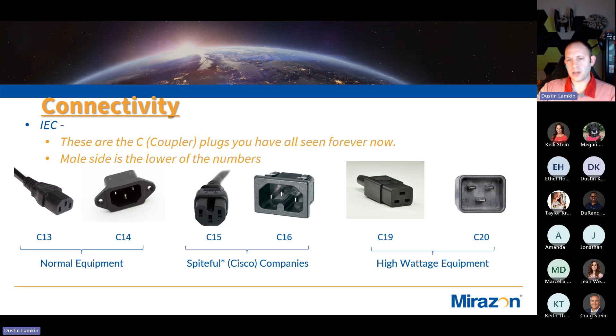So, PDUs—why do we need them? PDUs add more receptacles to your UPSs. Generally the small UPSs have their own NEMA 5-15 connectors on them, we'll talk about that more later. But when we get into the large non-desktop UPSs, a lot of those only have the large amperage locking connectors on them. They might have one or two consumer rated plugs too, but generally PDUs are what distributes your power to all your servers.